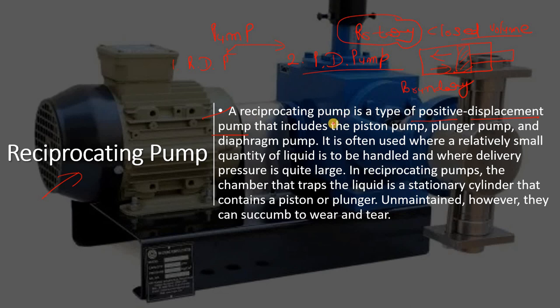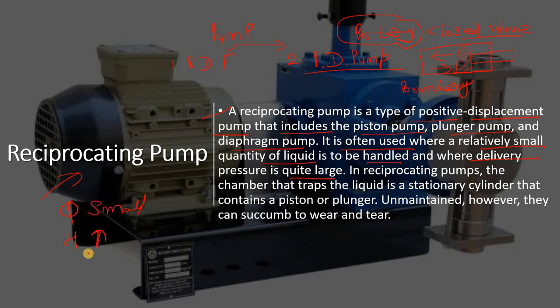A reciprocating pump is a type of positive displacement pump that includes a piston, plunger, or diaphragm — these are the heart of the reciprocating pump. It is mainly used where a relatively small quantity of liquid is to be handled and the delivery pressure is quite large, meaning small Q but high head.